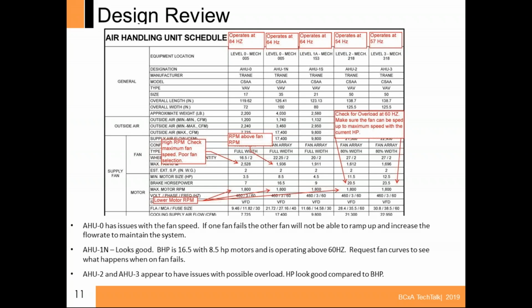On air handler 2 and 3 on the far right, one operates at 54 hertz, and the other one operates at 57 hertz. Now this is where we start looking at those voltages, okay? So let's look at the ratio of his horsepowers to the ratio of his speeds. And he has 20 horsepower brake on AHU 2 and also on AHU 3. Looks like we have our horsepower, looks like it's in a good place, but we should probably go back and calculate it and make sure that if one fan fails, we can actually ramp the other one up a little while. I'll discuss how I like to ramp them up when I get them all set up to work.